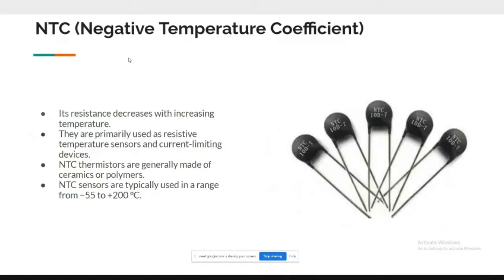NTC, negative temperature coefficient: its resistance decreases with increasing temperature. They are primarily used as resistive temperature sensors and current limiting devices. NTC thermistors are generally made of ceramic or polymers. NTC sensors are typically used in a range from minus 55 degrees to plus 200 degrees Celsius.